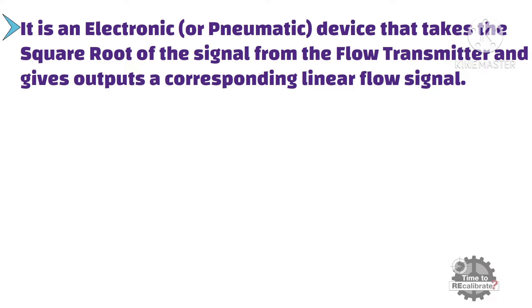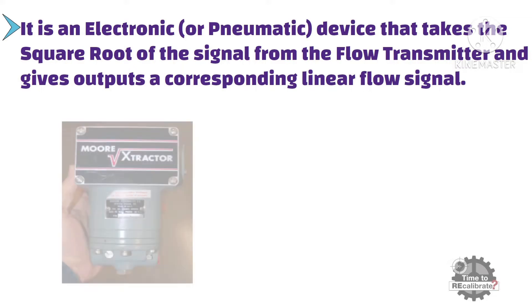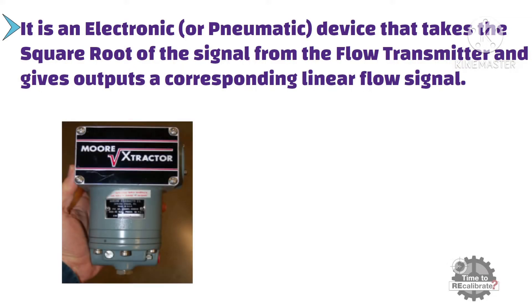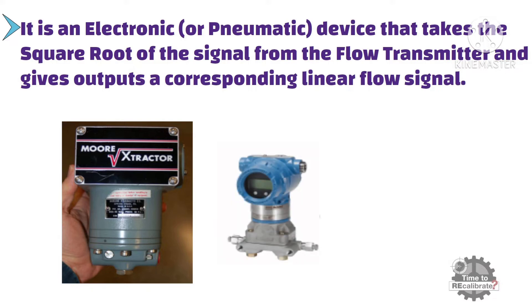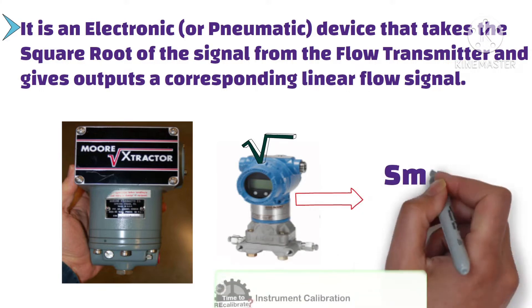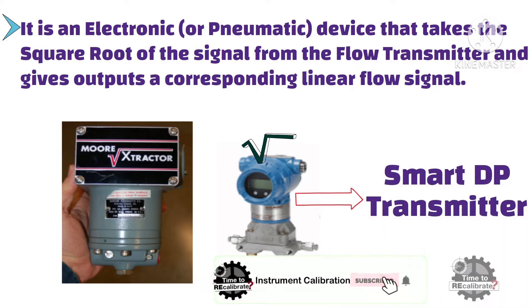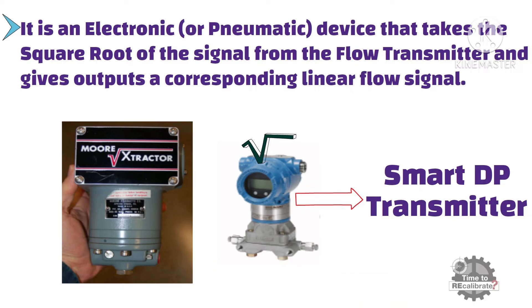In other words, it takes the square root input milliampere signal from the DP transmitter and converts it into a linear milliampere signal. As you can see from the picture, the square root function was performed in a separate device called a square root extractor in the days of pneumatic instrumentation. Nowadays, all smart DP transmitters come with a square root extractor function — the user can select the square root extractor function from the transmitter.